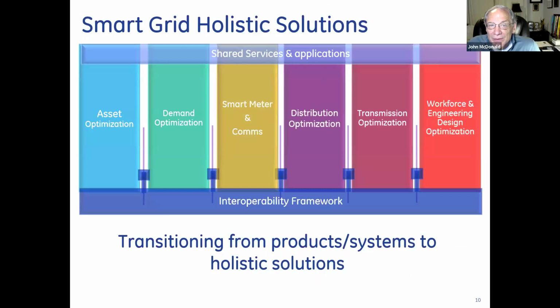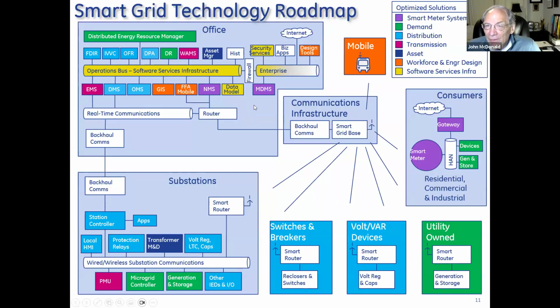So these are the 6 holistic solutions. This is the roadmap of the 6, color-coded. So, for an example, take a look at the light blue boxes, that's distribution. You can see when I said that success depends on technology, standards, and policy, you can see why standards are so important. These light blue boxes could be from different vendors, but yet all of this equipment needs to be able to communicate with each other and exchange information with each other. For that to be successful, the components have to comply with the same standard or sets of standards. Because you have components up in the office or control center, upper left, lower left, the substations, and lower middle, this is equipment downstream of the substation on the feeders, okay?